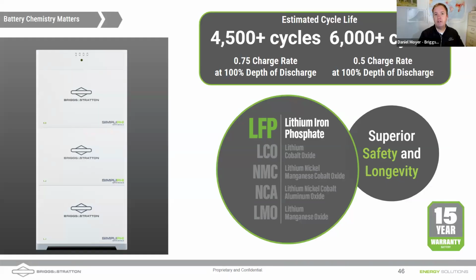15-year warranty on this battery, unlimited cycles, 100% depth of discharge with no throughput clause. Although we have unlimited cycles, we do have some estimated cycle life based on the rate at which you charge and discharge the battery. A 0.5 charge rate, that's a 2-hour charge rate, C over 2. If you charge the battery in 2 hours or discharge the battery in 2 hours, you can expect 6,000 cycles. If you're hammering on the battery a little bit more, with an hour and 15 minutes charge or discharge, you're going to get a little bit fewer cycles. Although we say 100% depth of discharge, I recommend an 80% depth of discharge just to leave a little bit of juice in the battery. We're leveraging that lithium iron phosphate chemistry.